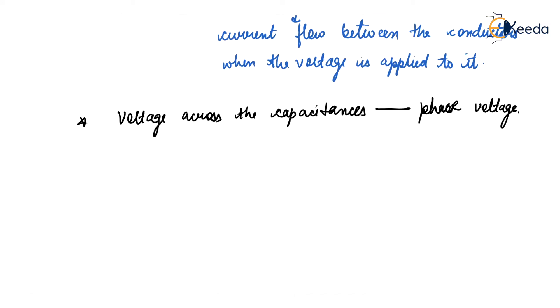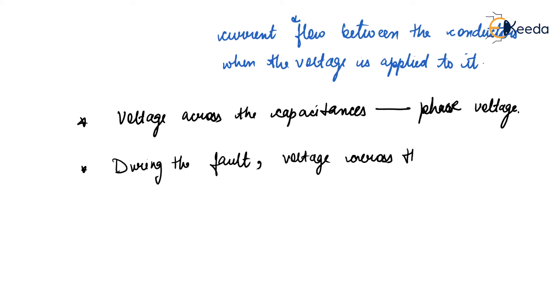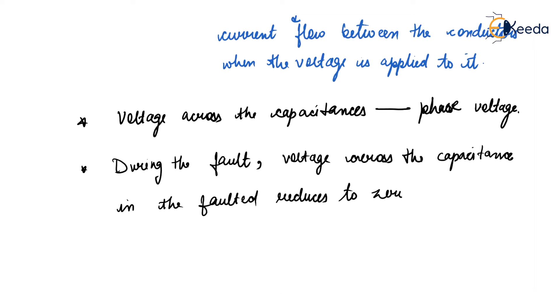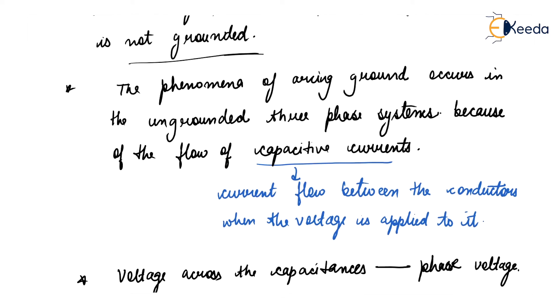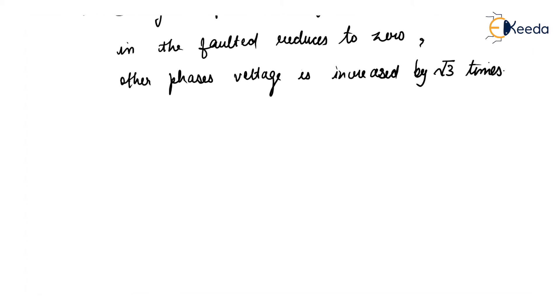So during the fault, the voltage across the capacitance in the faulted phase reduces to zero, while in other phases the voltage is increased by root three times. This is the arcing ground definition.